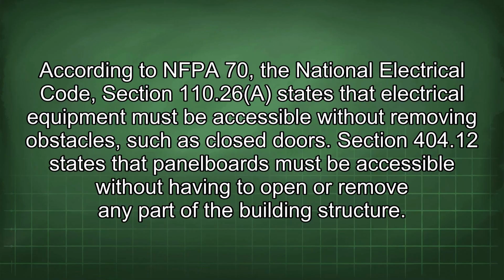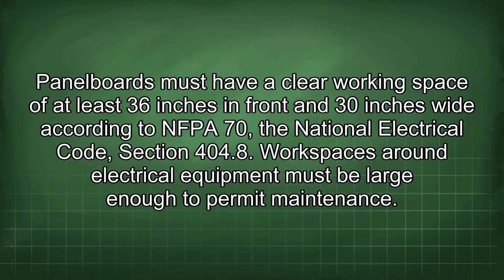According to NFPA 70, the National Electrical Code, Section 110.26 states that electrical equipment must be accessible without removing obstacles, such as closed doors. Section 404.12 states that panel boards must be accessible without having to open or remove any part of the building structure. Panel boards must have a clear working space of at least 36 inches in front and 30 inches wide according to NFPA 70, the National Electrical Code, Section 404.8. Workspaces around electrical equipment must be large enough to permit maintenance.